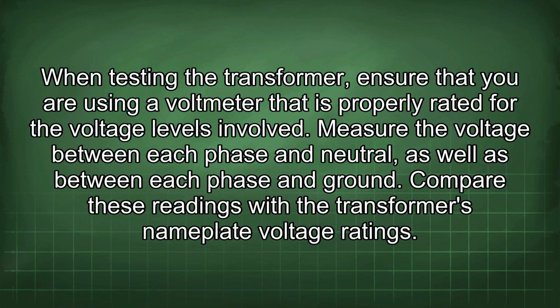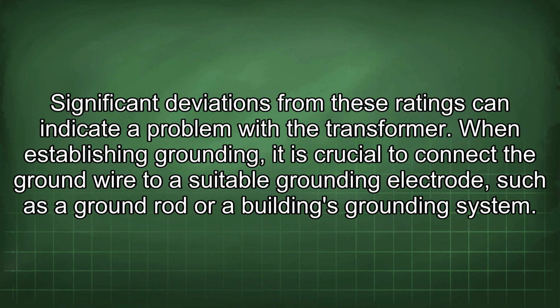When testing the transformer, ensure that you are using a voltmeter that is properly rated for the voltage levels involved. Measure the voltage between each phase and neutral, as well as between each phase and ground. Compare these readings with the transformer's nameplate voltage ratings. Significant deviations from these ratings can indicate a problem with the transformer.